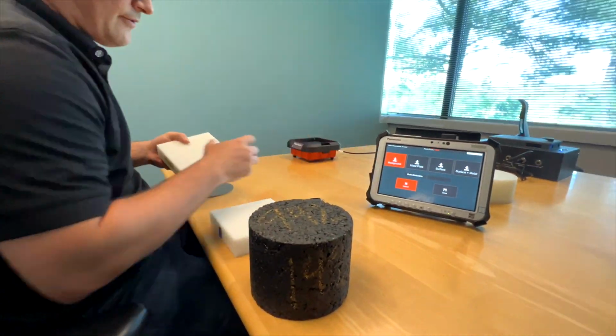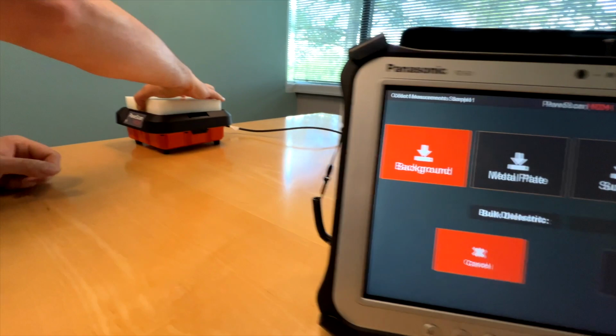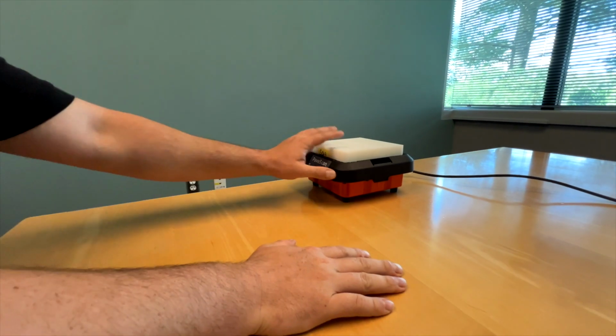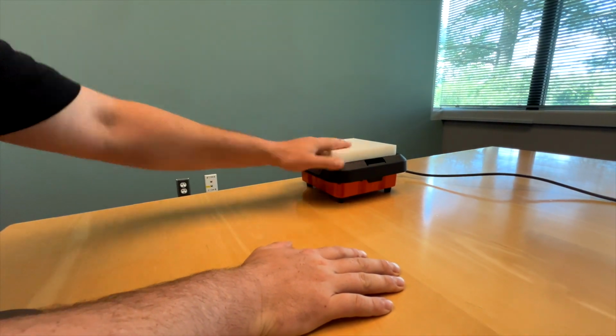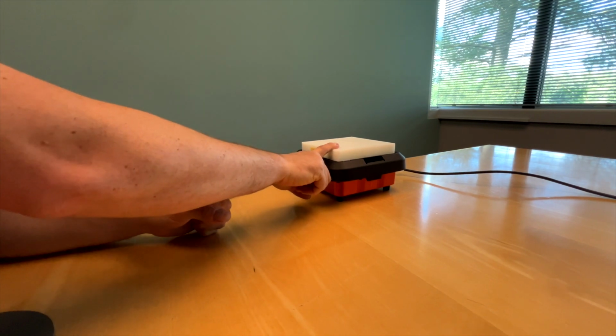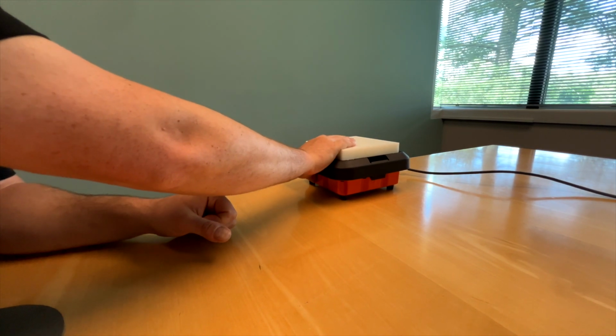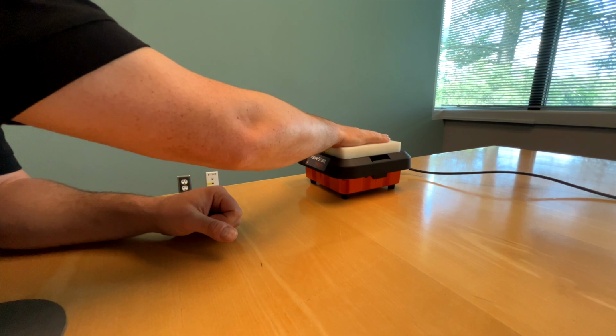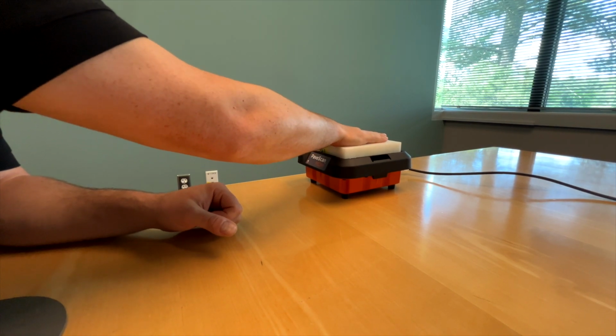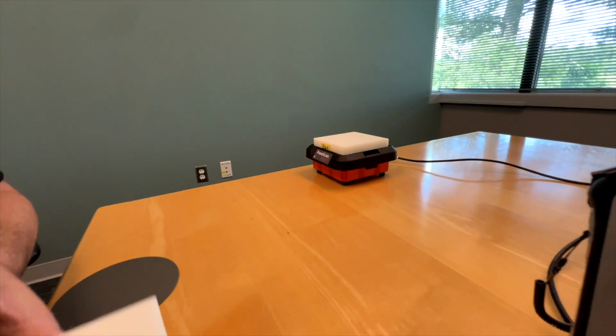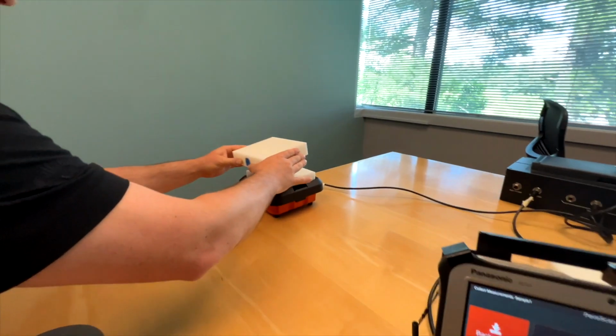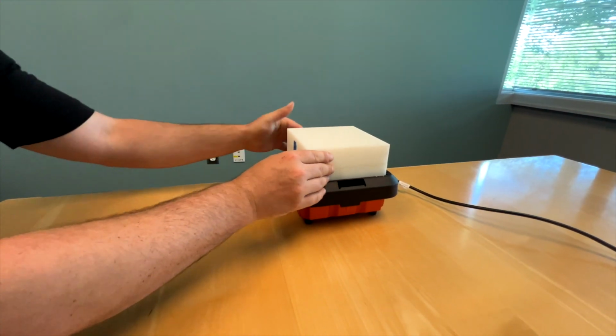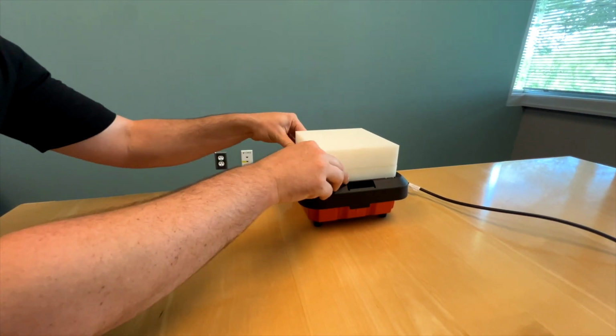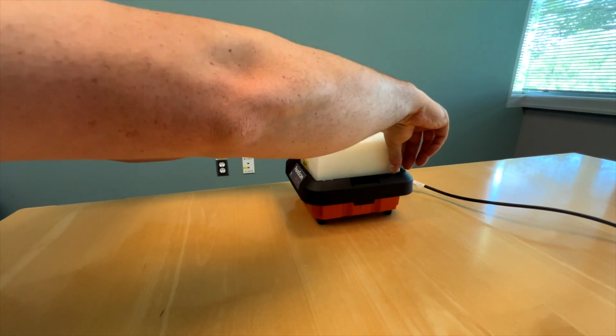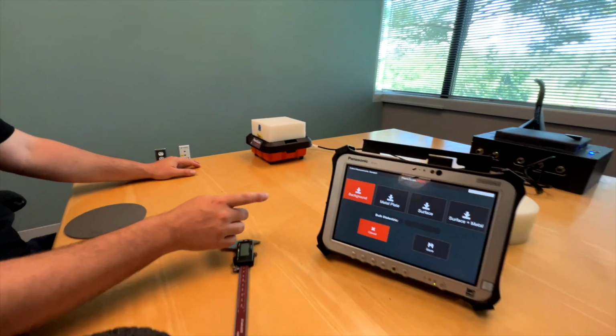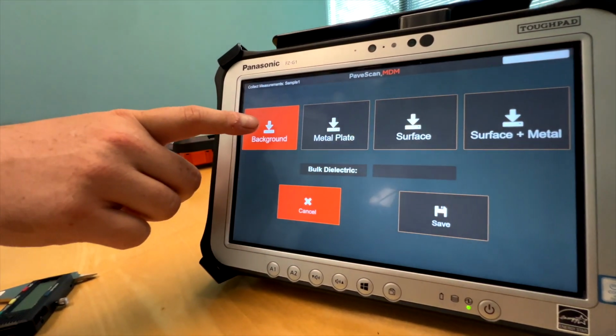First, for background, I'm going to place one Delrin block on top of the sensor. It should fit in there nice and snug. This block of Delrin is never going to leave here during the calibration process. There's always going to be one block of Delrin right here up against the sensor. For this first measurement, I'm going to place the second block of Delrin right on top of it. I'm going to make sure it's lined up nice and even. And then on the software, I'm going to hit background.